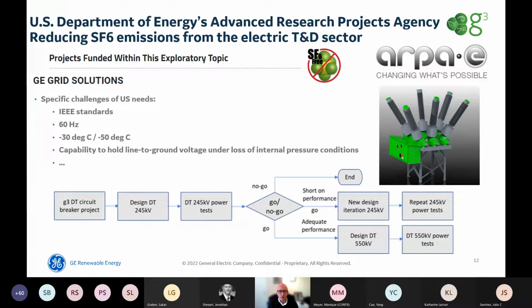The capability for a breaker to hold line-to-ground voltage under loss of internal pressure—so you lose completely the pressure of your tank, of whatever gas insulated medium you have in your tank—are you still able to hold line-to-ground voltage right under that? It's one of many key performances that has an impact on the size and dimensions, the size of the concrete.